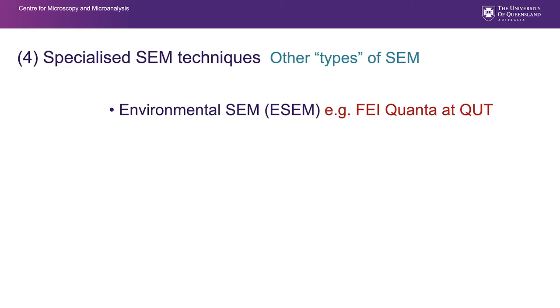First on the list is environmental SEM, or ESEM. We don't have one of those here, but they are interesting in that they were developed to allow CSIRO researchers to look at wet sheep's wool. They allow a poor vacuum into the chamber and use the electron beam to ionize those atoms, producing positive ions and electrons. The positive ions are attracted towards electrons building up on the sample surface and can be used to dissipate charge, allowing operation at quite high pressures to image insulating and difficult samples.